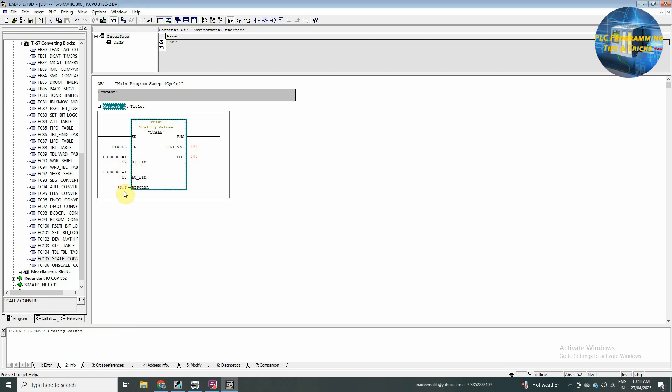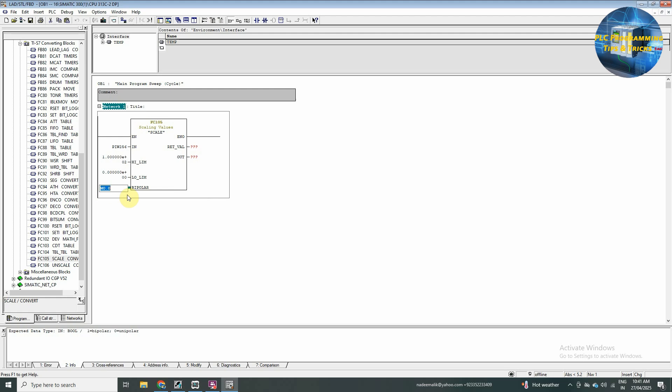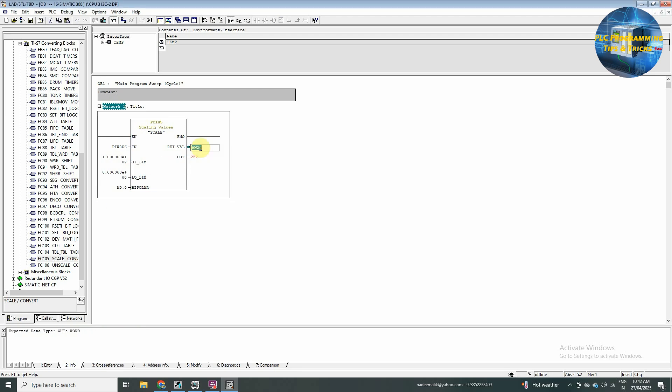In the bipolar scale, we can scale the negative and the positive kind of input to 250.0. So, we will uncheck here and give 0 to deactivate this bipolar function. In the return value, you will insert memory word MW 20.